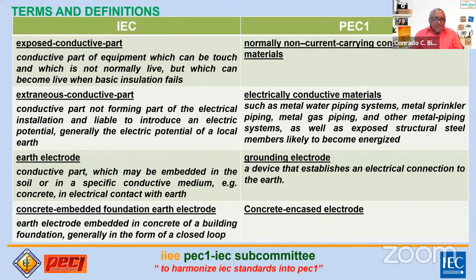Napakahalaga nito. So in IEC, conductive part of equipment, ito exposed conductive part. This is the conductive part of equipment which can be touched and which is not normally live but which can become live when basic insulation fails. Sa PEC naman, nakalagay doon sa 2.50, normally non-current carrying conductive materials. So what are these? Ito yung body ng motor, electric motors, panel boards, metal parts. Okay, ito yung mga conductive part of the equipment. So pag nagkaroon ng insulation fault, kunwari sa winding o sa mga internal insulated wires sa loob ng equipment, at yun ay nag-fail at pumunta doon sa body, ito na yung conductive part. So nagkakaroon ng problema, nagiging live siya. So yun ang exposed conductive part. Ito, medyo maiksi lang siya. Sa PEC, normally non-current carrying conductive, so masyado mahaba. Anyway, ito yung definitions niya.